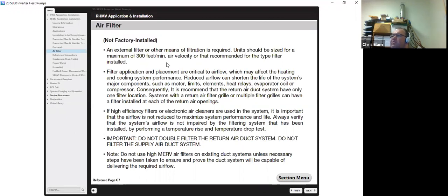Reduced airflow can shorten the life of system components, such as motors, limits, elements, heat relays, evaporator coil, or compressor. Consequently, it is recommended that the return air duct system only have one filter location. Systems with a large return air grill or multiple filter grills can have a filter at each opening. Down here it's an important note, do not double filter the return air duct system. You're going to drive your static pressure crazy.